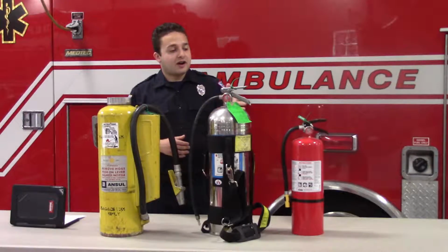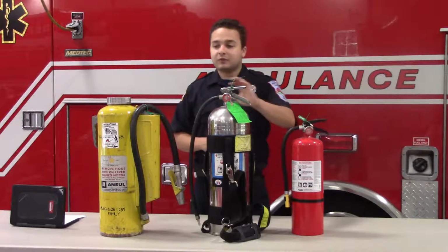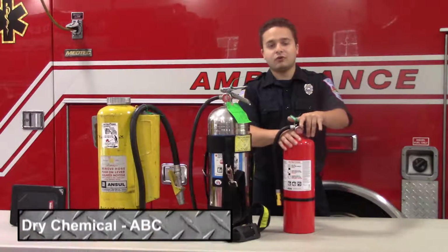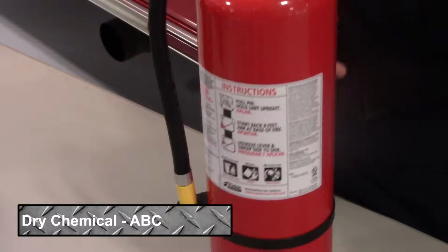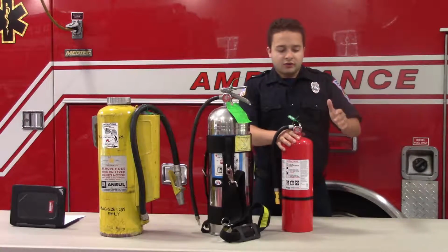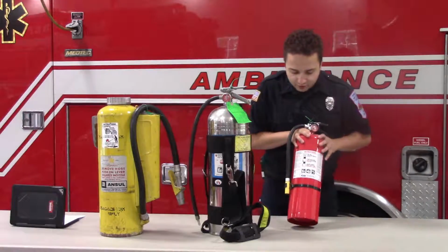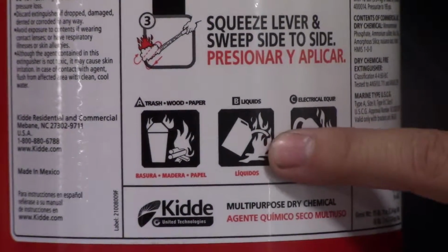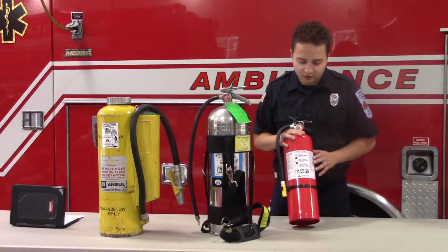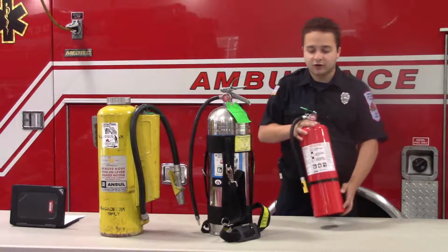So now that we know the different types of fires, we need to know what type of extinguishers to use on those fires. Here are some of the common extinguishers that we have. Most commonly, the extinguisher you're going to see is this dry chemical ABC extinguisher. It is just dry chemical inside, ammonium phosphate, with also compressed air. These are good on Class A, B, and C fires, as it says in its name. You can also look on the label on the front and see the pictures for ABC. All fire extinguishers have to have pictures and labels to state what fires they work on. It also gives you a step-by-step of how to use a fire extinguisher, which we'll talk about more in a few moments.